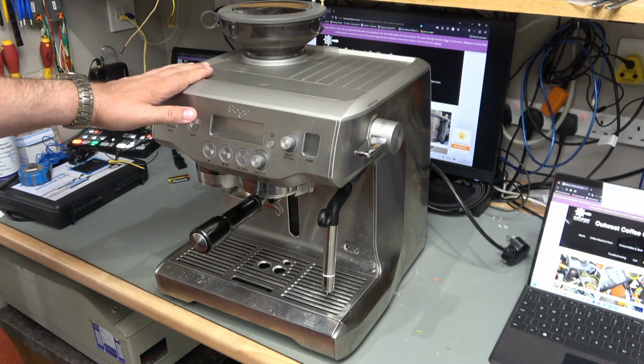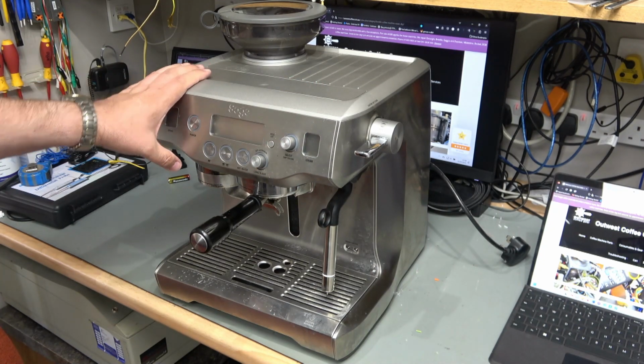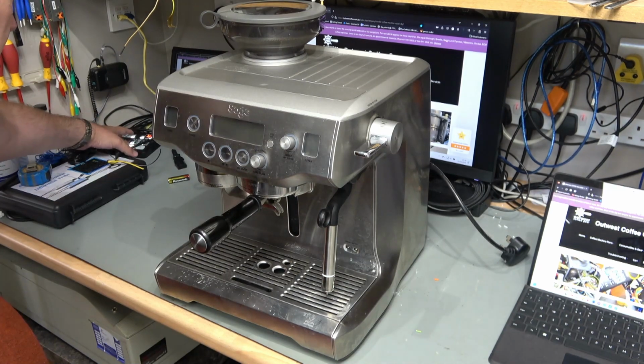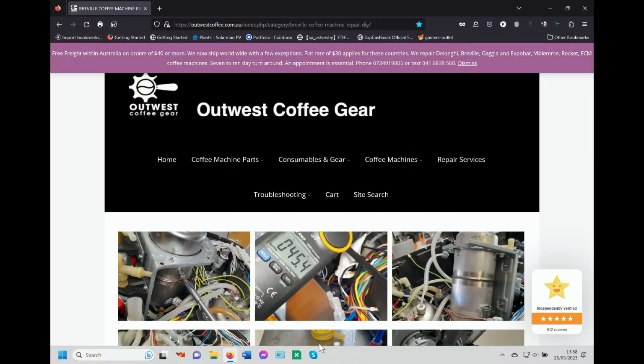So I've had a good look around, and one of the sites I've been looking at is this guy here at Outwest Coffee Gear. They've got quite a lot of information about repairs, and I've also looked at quite a few forums for this same problem. What happens is it gets to 93, continues to 94, 95, 96, and then it pretends it's gone to 93, but the heater is still operating, still getting hot. If I turn it off and then on again, it immediately shows a temperature reading of 100 centigrade.